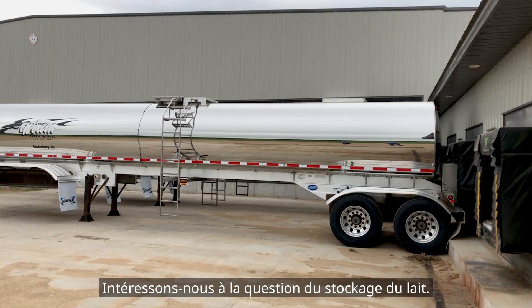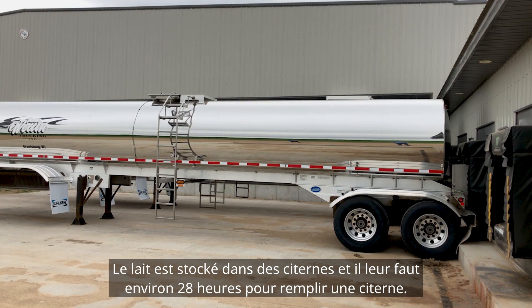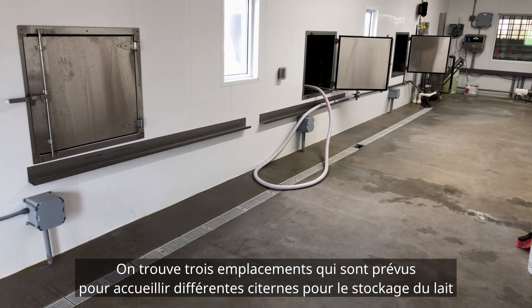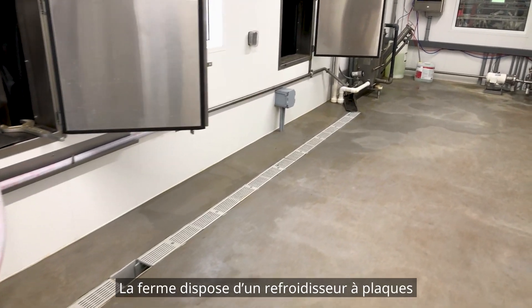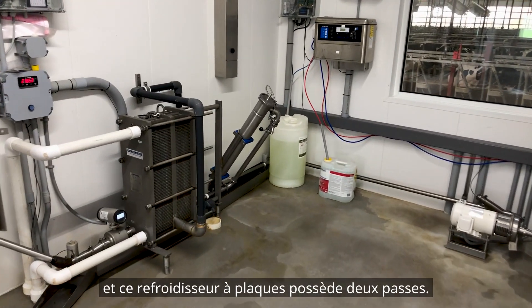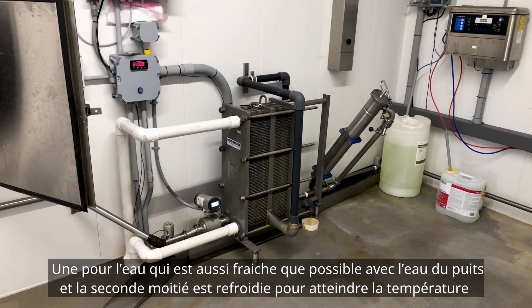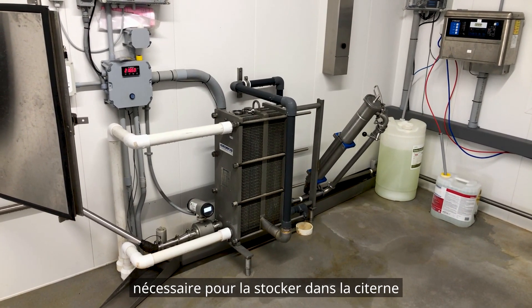Here at Minglewood Dairy, from a milk storage standpoint, everything is kept in tankers and it takes about 28 hours to fill a tanker. In the milk room you can see there are three bays so they could have three different tankers ready to accept milk. Being that it is direct load, they have to have a plate cooler, and this plate cooler has two passes. One is for water — they take it as cold as they can with well water — and then the second half is chilled, getting it down to the temperature needed to store it in the tanker.